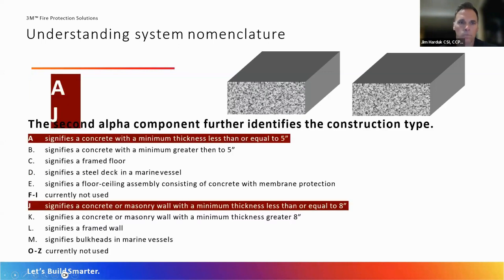Next slide. The second alpha component further identifies the construction type. So in this example here, anything with an A would signify a concrete floor with a minimum thickness less than or equal to 5 inches. A J signifies a concrete or masonry wall with a minimum thickness less than or equal to 8 inches. If you remember, as I mentioned before, when these manufacturers are running these tests, they will try to group together different configurations. It's a little bit more cost effective that way to do, and it makes it a little bit easier to catalog all this information. So this example that I'm going to show you here, you'll notice that this can be used for a concrete floor or wall assembly. Next slide, please.